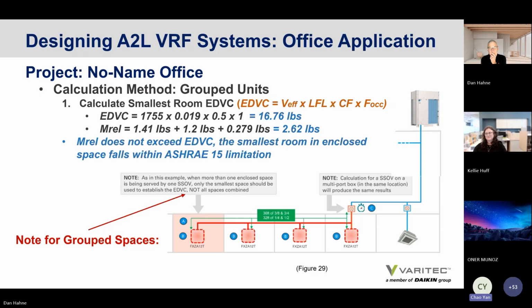Last question. The shaft enclosure requirement. There is an addendum for ASHRAE 15 coming out late May, I believe, 6 or 7 weeks ago. I think they revised that. That's addenda, it would be addenda A. You're talking about addenda A for ASHRAE 15? Yes. Sorry, we didn't have enough time to go over the latest slides here, Dan, but a shaft enclosure is not required as a result of the recently published addenda A, and a pending addenda B will make it so that if you choose to use a shaft, ventilation will not be required for section 9.12.2.2.